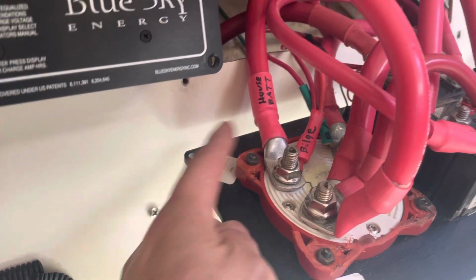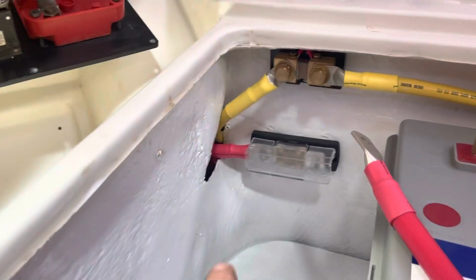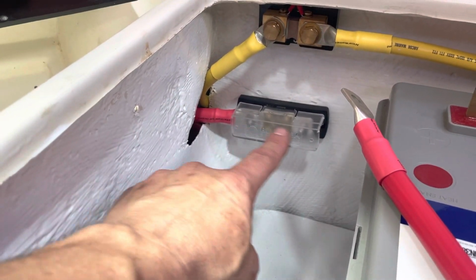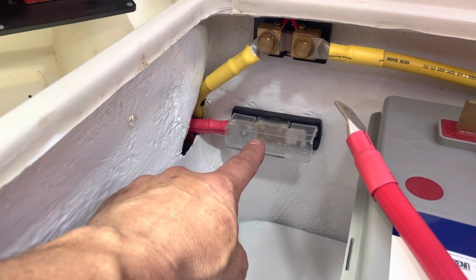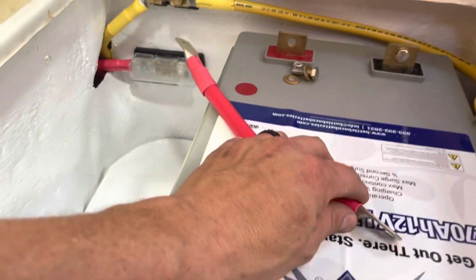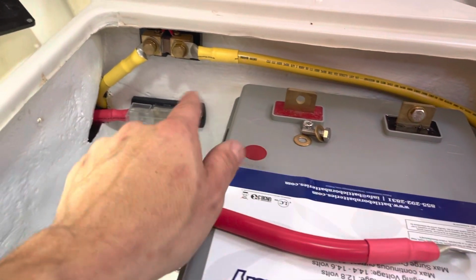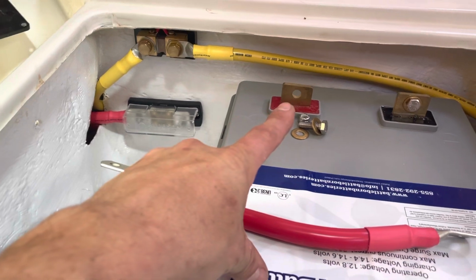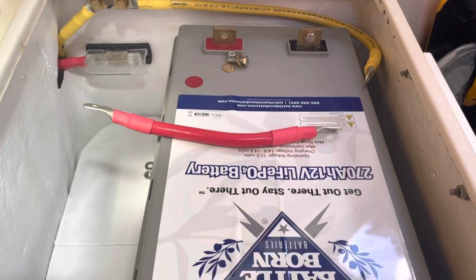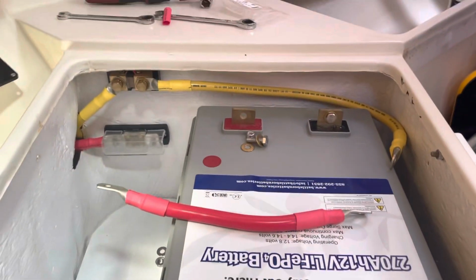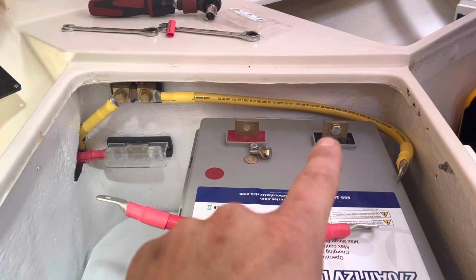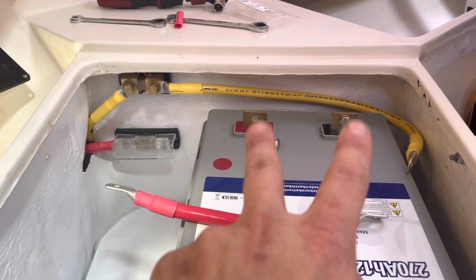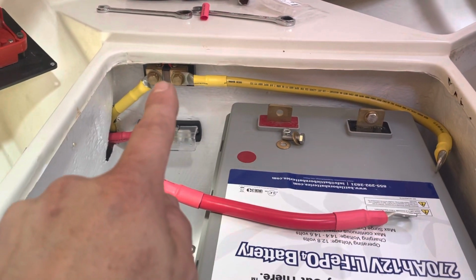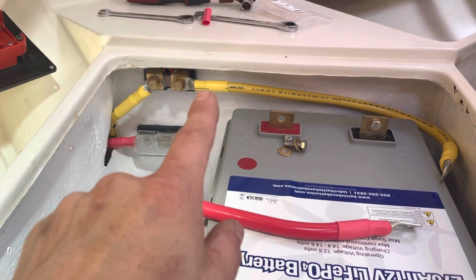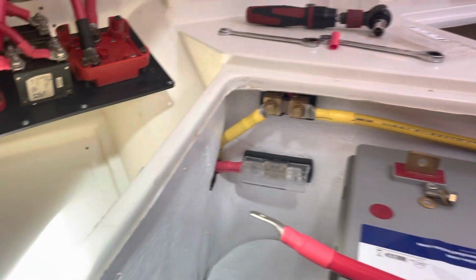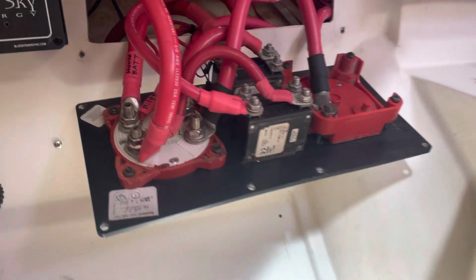This big 2-aught cable here comes over to this 300 ANL fuse holder - there's a 300 amp ANL fuse in there - and then this cable I just made connects from the fuse holder to the positive terminal on this 8D battery from Battleborn. The ground cable will connect there, and that's the only thing that's going to be connected to the battery. That goes to the shunt, and then on the back side of this wall is the large DC bus bar for the negative.